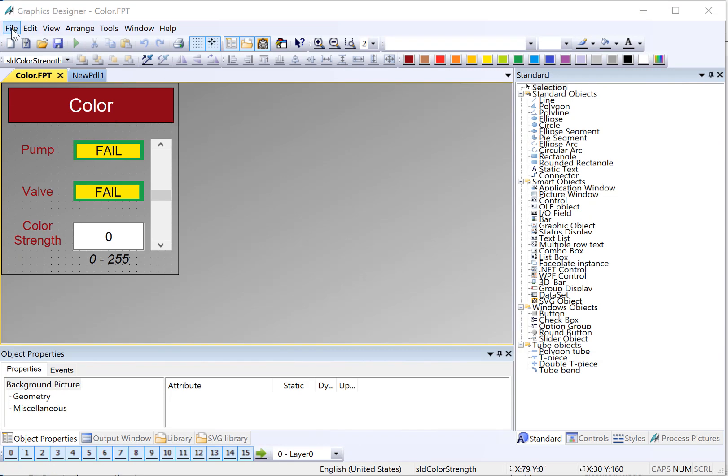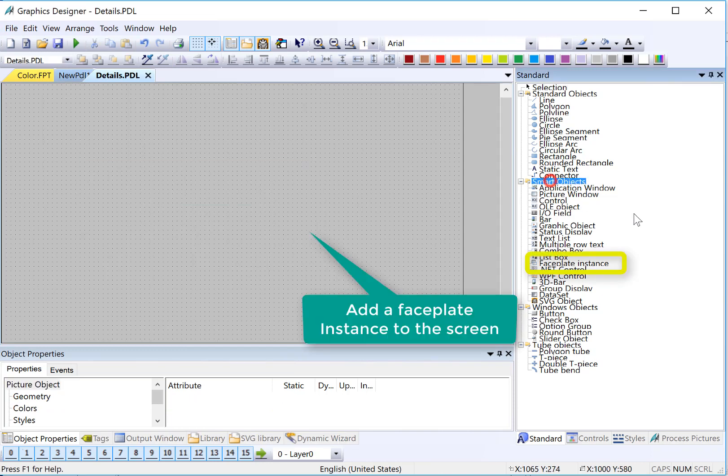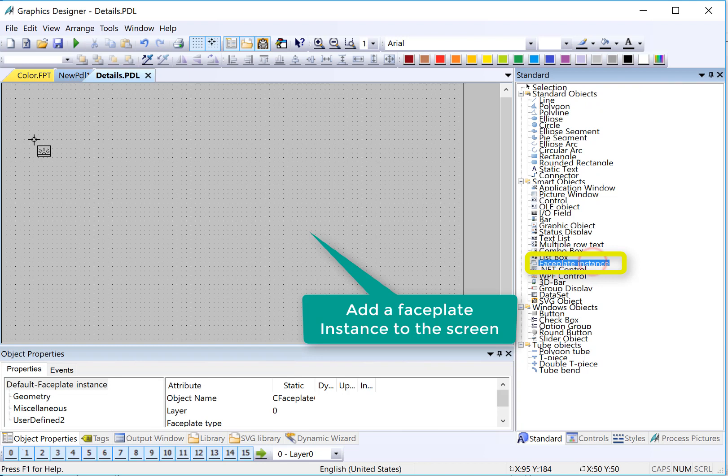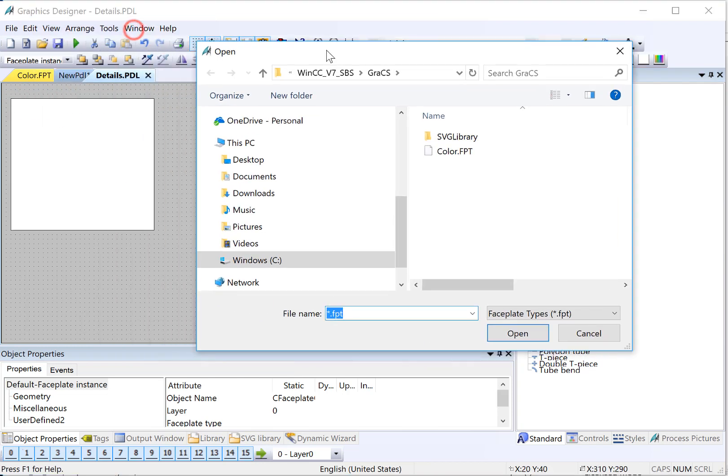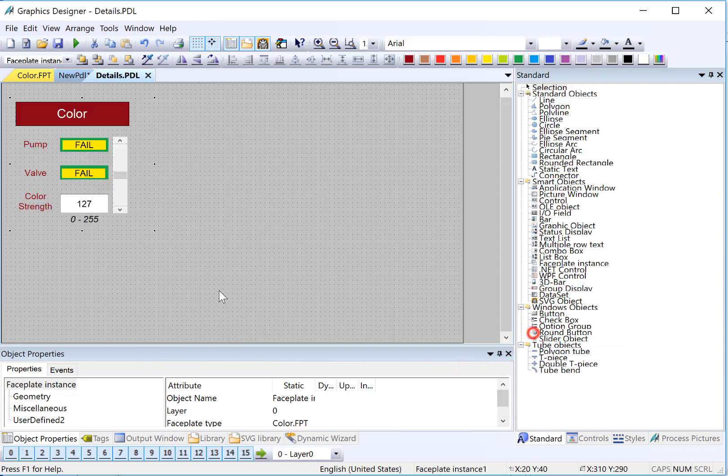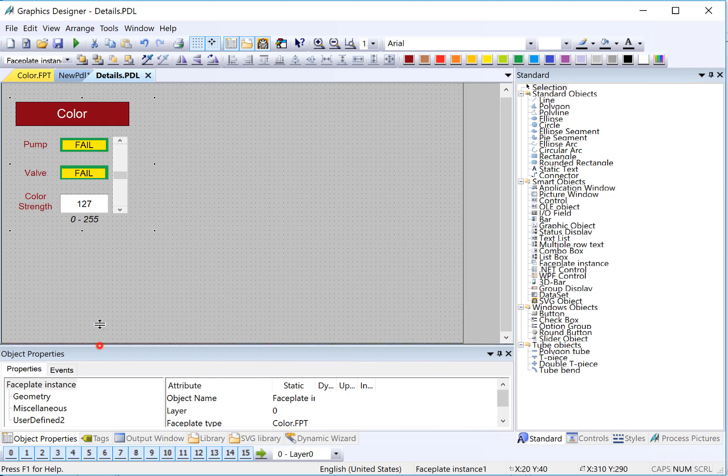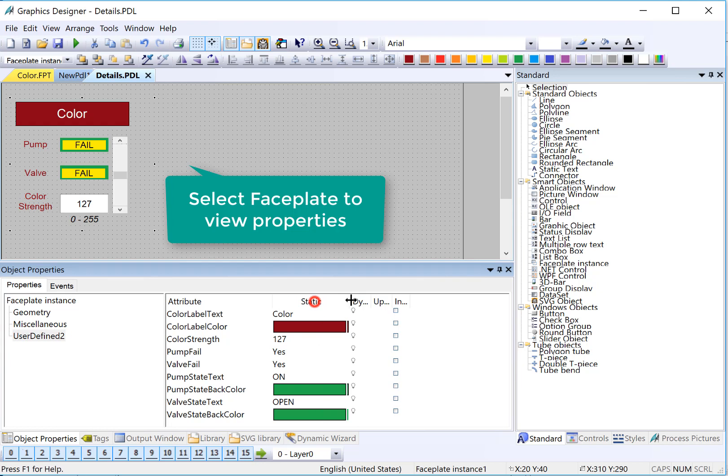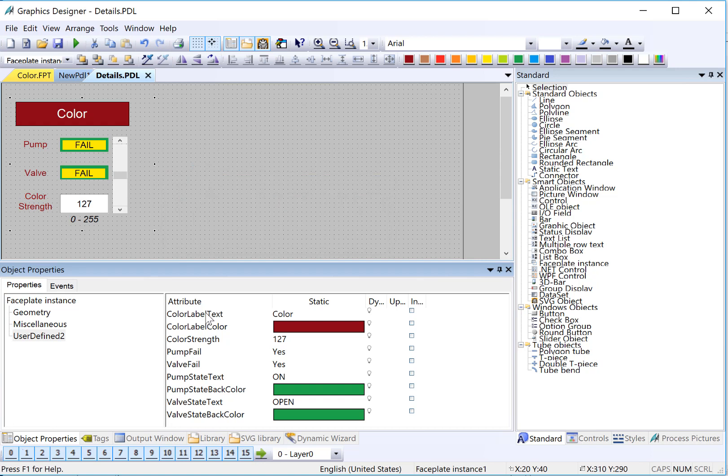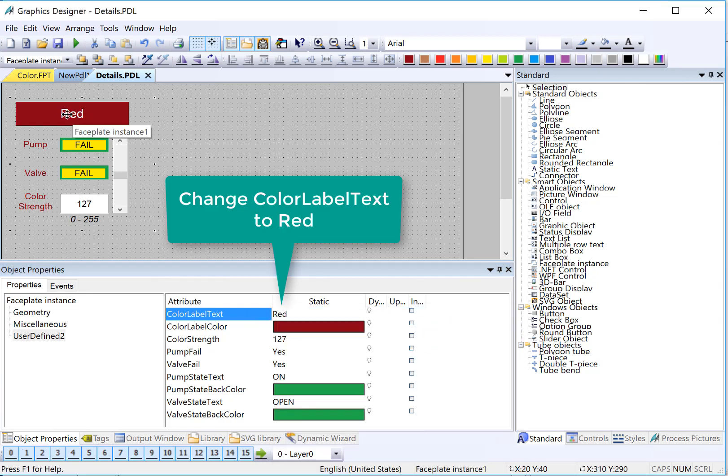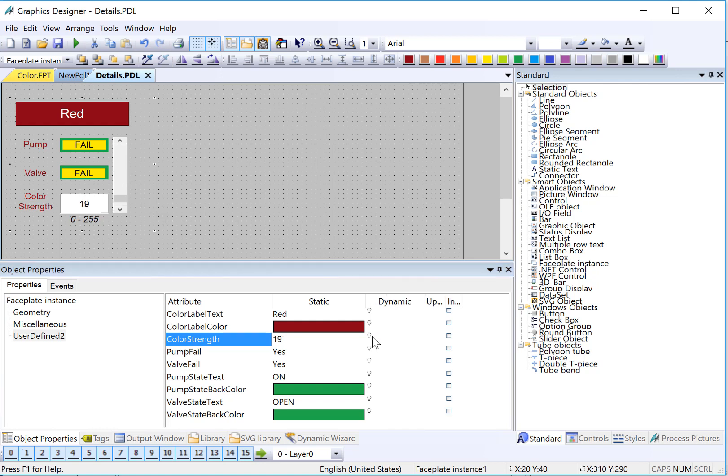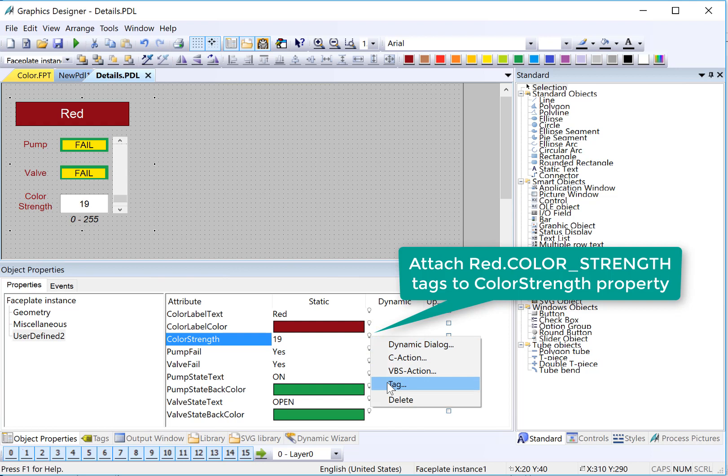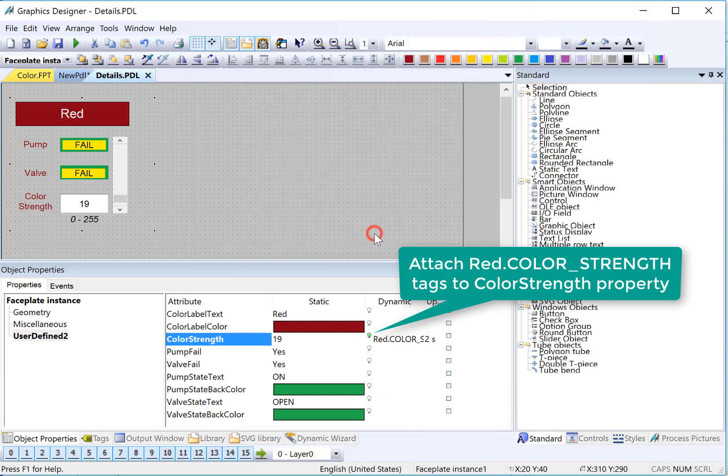I'll get rid of our placeholder text. And then under smart objects, find the faceplate instance and we'll just drag one out. Now it's going to ask us what faceplate we want to connect to. And of course, we want to connect to our color FPT. And there's our object. Now notice that we have the object selected. If we look at our properties, those are all the properties that we just configured. So we can treat this like any other object and assign tags or do dynamic dialogs. Since this is going to be our red, then we'll do green and blue. My color label text, I can just edit this directly and just type in red. Our default color background is red. We don't need to change that. Our color strength is hooked up to both our IO field and our slider. So we'll just hook up our tag. We'll right-click, choose tag, and then we'll just hook up our red color strength.